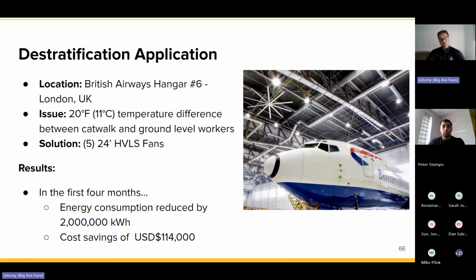This is an extreme example, somewhat like I was alluding to with the hangar study. This was for British Airways, and they were seeing about $114,000 in cost savings in the first 4 months, just by reducing the amount of mechanical heating for that space. A significant stratification effect using 5 fans to destratify that building — their ROI would have been within months. It seems crazy, but this is something we can effectively do pretty consistently, especially as you get into these larger, poorly insulated buildings.